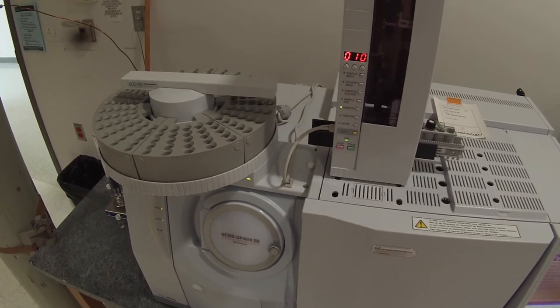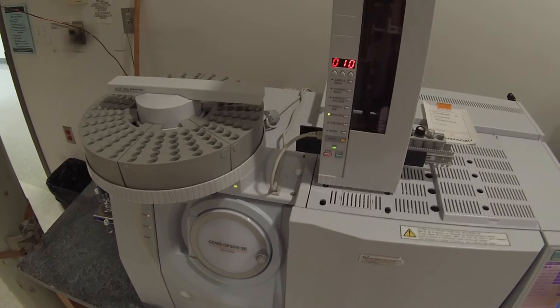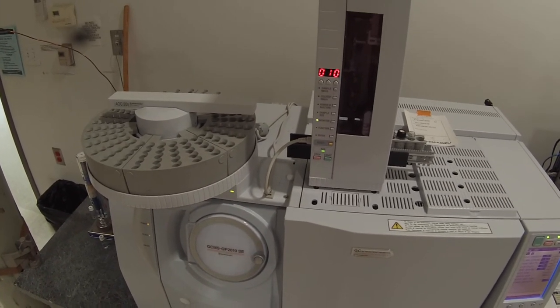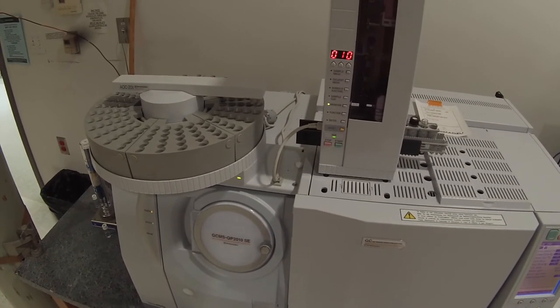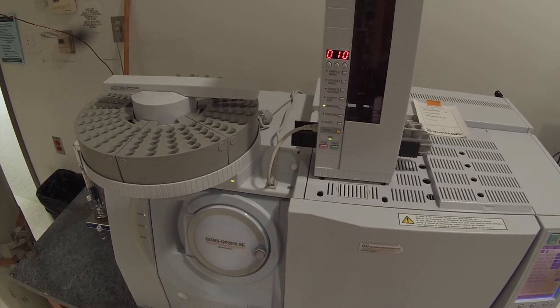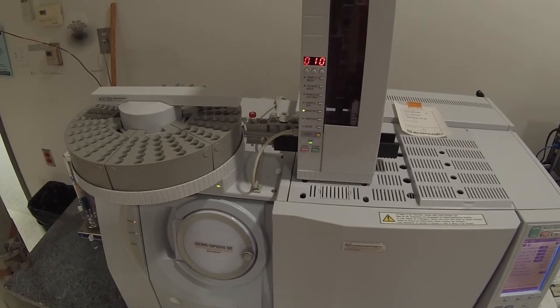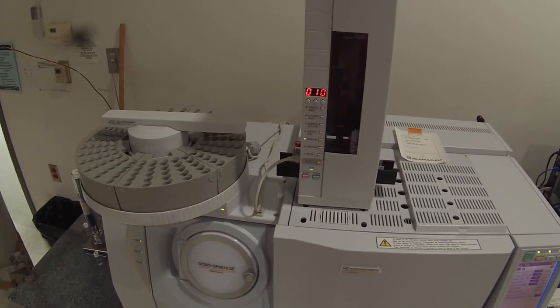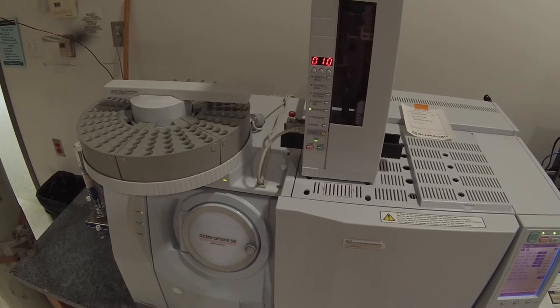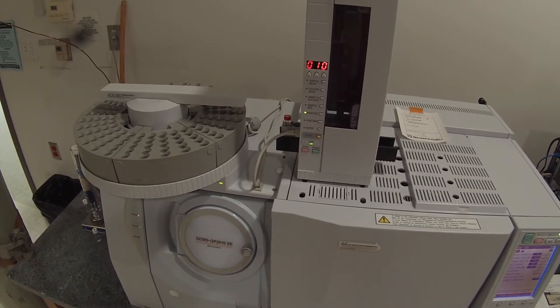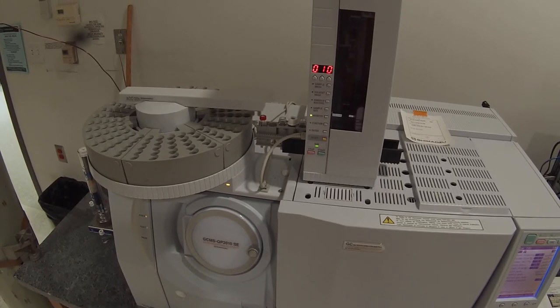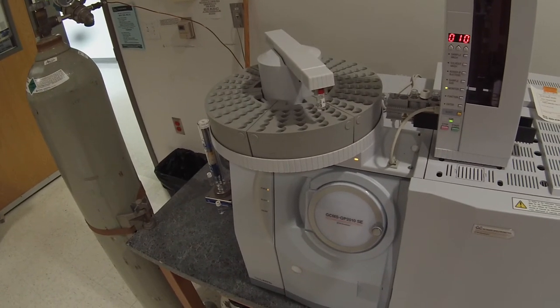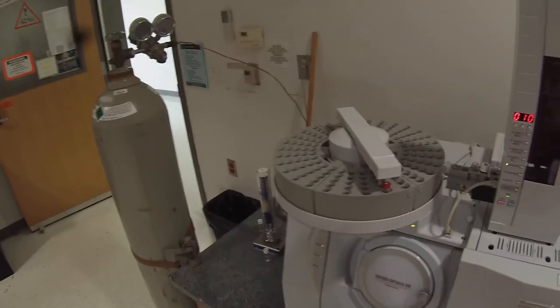And now it's going to pull our sample up and pump 3 times to get the air bubbles out. So you can see that it's going up and down pretty rapidly. Now it's going to pull that 0.1 microliters up. It's going to push it through the septum, depress the plunger, and start the run. And now it's going to wash the syringe a couple of times with dichloromethane just to make sure it's clean for the next run. And it's going to return the sample vial to slot number 10. And if this batch file were set up so that it were running 14 or 15 samples overnight, when it was done with this first sample, it would go to the next vial.